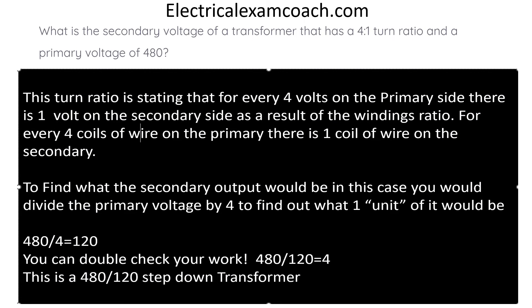This turns ratio states that for every 4 volts on the primary side, there is 1 volt on the secondary side, as a result of the windings ratio — for every 4 coils of wire on the primary side, there is 1 coil on the secondary side. To find the secondary output, divide the primary voltage by 4. We take 480 divided by 4, which equals 120. You can double-check by dividing back: 480 divided by 120 equals 4. This is a 480/120 step-down transformer.